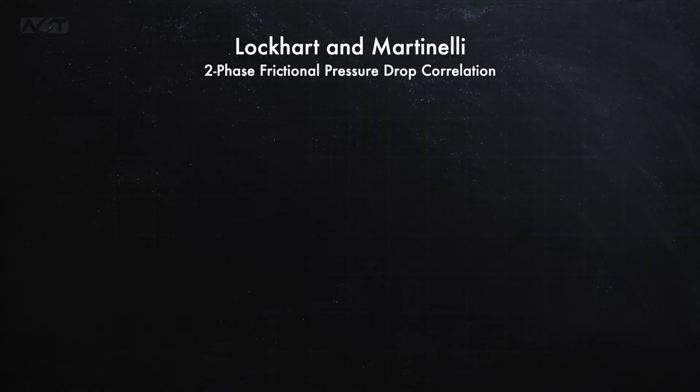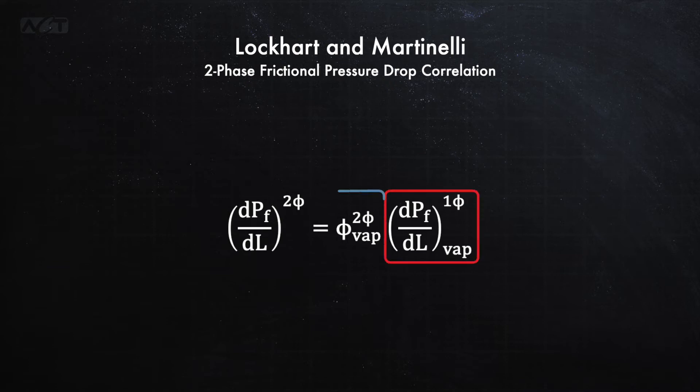For the regions with 100% liquid or vapor flow, standard Darcy friction factor equations are used for the tubular flow frictional pressure drop. However, in the two-phase flow regimes, the pressure drop calculations are a bit more difficult, and so we had to use some empirical correlations. Lockhart and Martinelli introduced what is probably the most widely used correlation, and this correlation adjusts the vapor phase pressure drop by a flow-dependent correction factor to arrive at the two-phase frictional pressure drop.